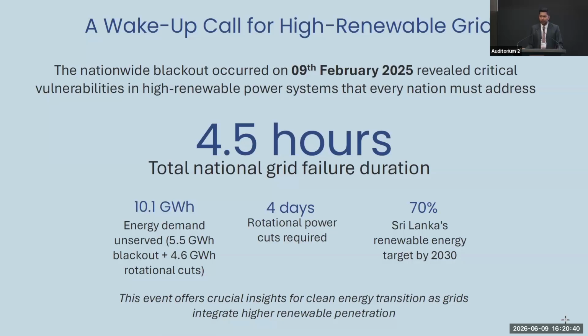So this gave Sri Lanka a wake-up call regarding being a high renewable grid. This national blackout occurred on a Sunday, in a situation of low demand and high renewables. The restoration of the system took more than 4 hours and 30 minutes. As a result, the system was unable to meet a total energy demand of 5.5 gigawatt hours directly due to the blackout, and another 4.6 gigawatt hours due to the rotational power cuts that we had to impose because of the unavailability of a large 900 megawatt coal power plant. It was unavailable for 4 days because it tripped during the blackout.